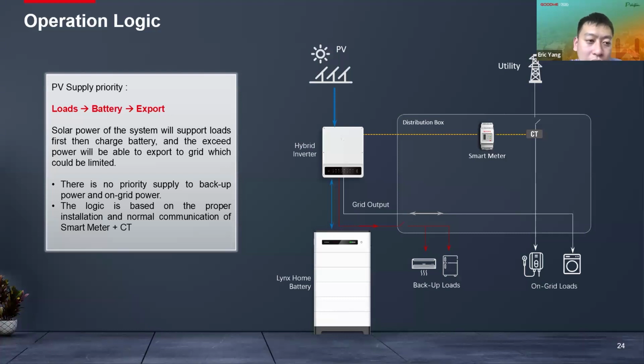And for the PV supply priority, by default, PV will support the loads first. When the grid is available, it will support both backup loads and on-grid loads. And if there is more power, it will charge the battery.